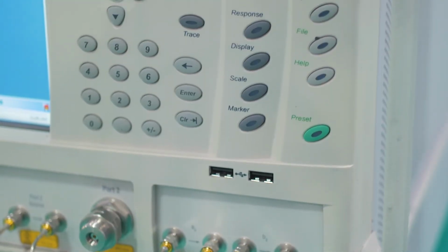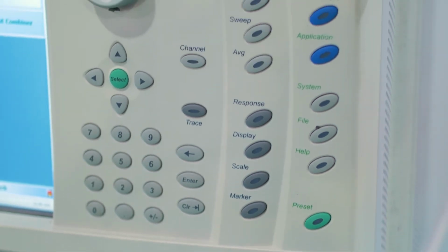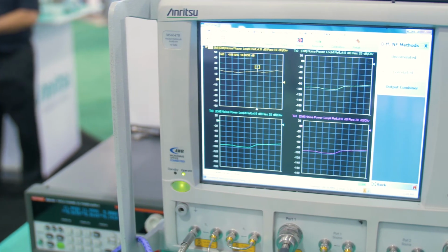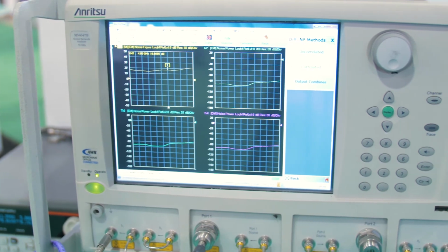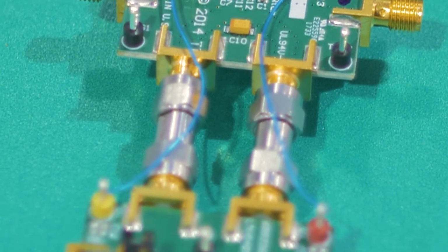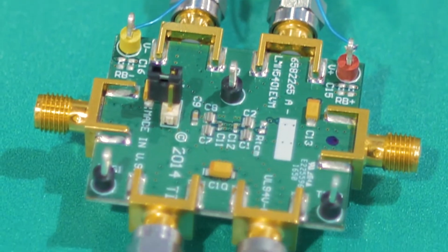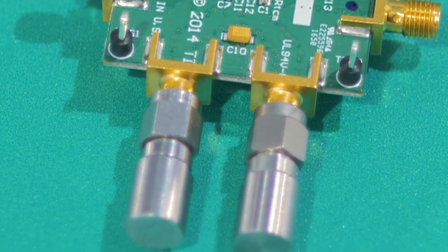What's difficult to do about a differential noise figure measurement like this? The reason it's a difficult measurement to make is that you have to have both samplers and everything turned on at the same time and looking at the measurement in real time. Typically it's a calculation that gets done in post-processing, and then you display it, so the results are not real time. By doing it differentially in real time, now you can get data in seconds compared to a longer time.